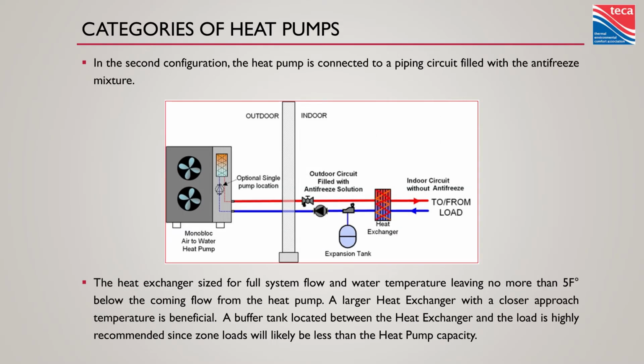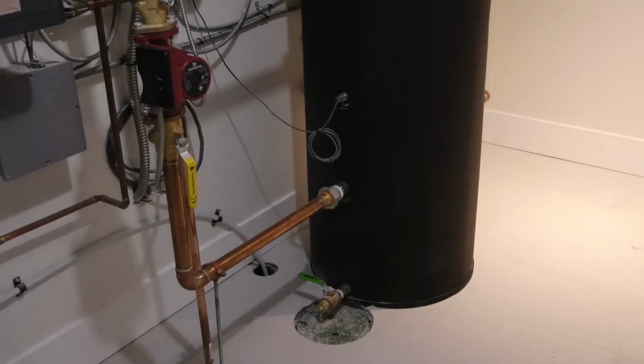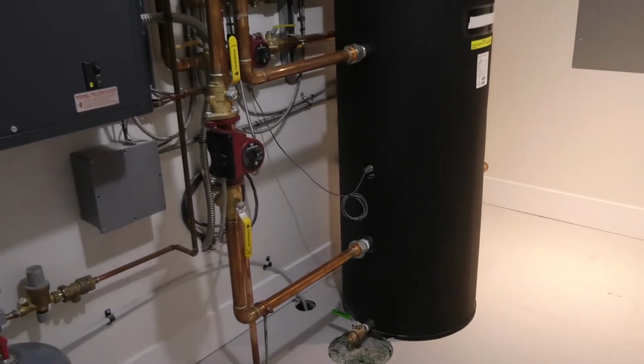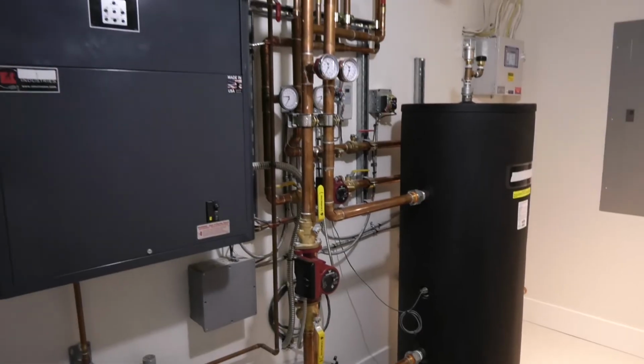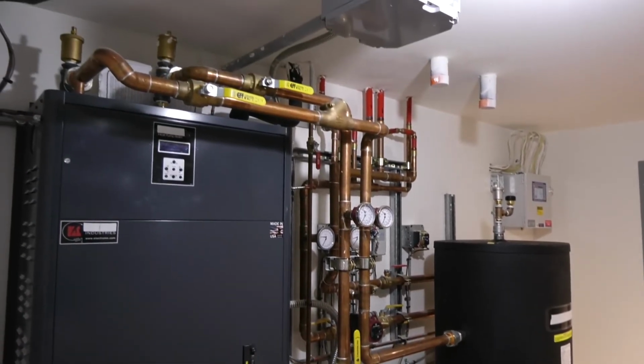Sometimes people don't like paying for glycol, so they like to isolate a small subsection of the hydronic system to just put glycol in that part and leave 100% water everywhere else. It can be done. You'd use a fluid-to-fluid heat exchanger to do it, but you also have to be careful with that. To transfer heat, water to water needs a difference in temperature.